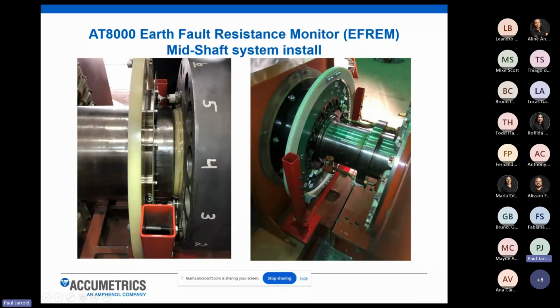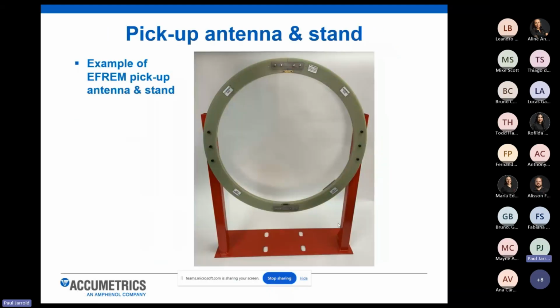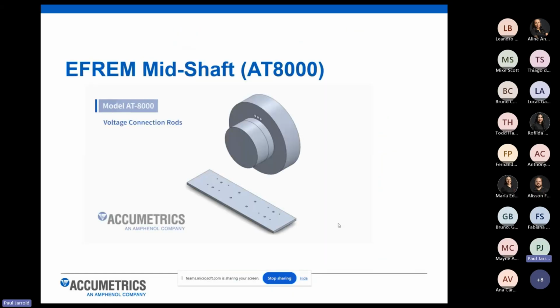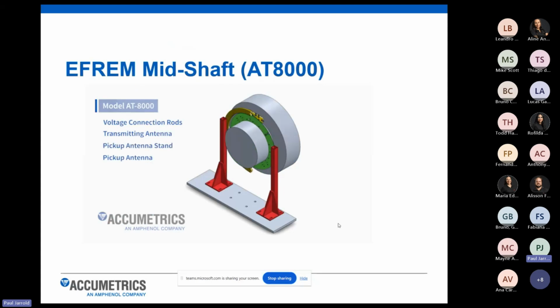So we provide the rotating transmitter component, the stationary pickup antenna, and then this mounting stand that's designed to be bolted directly to the brushless exciter floor and hold our pickup in place, and all the necessary hardware to mount everything in place is provided by us. That's what the pickup antenna and stand looks like. And this is just a 3D model to give you an idea. So those are the field voltage connections that go through the coupling flange. Then the transmitter collar pieces get installed on the exciter. The mounting stand gets in place, and then our pickup antenna is installed. And you can see the transmitter rotates with the shaft.